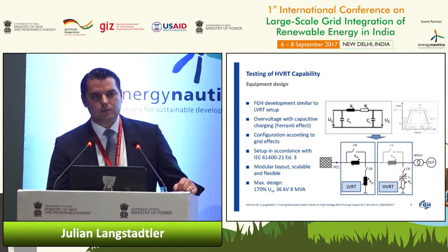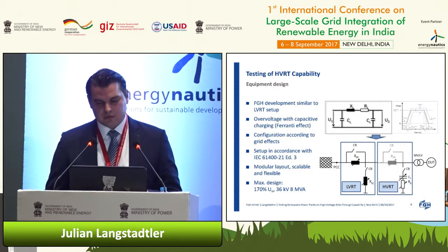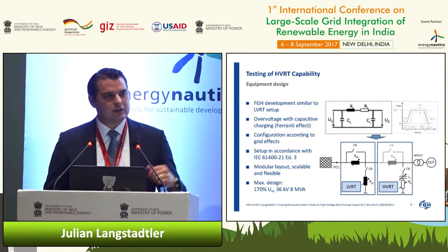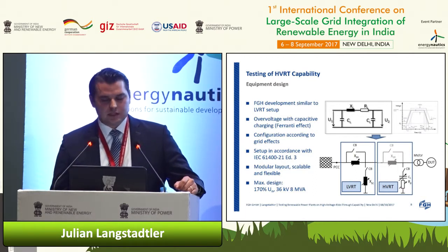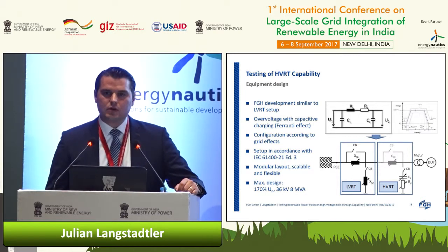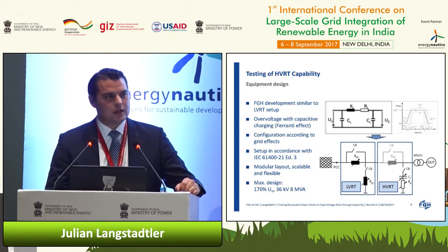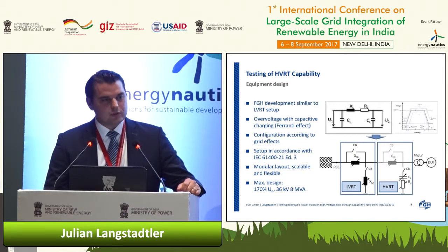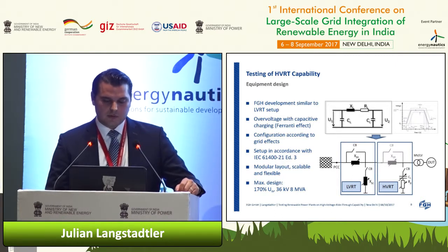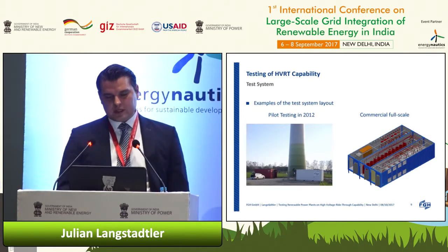That means, on the one hand, you have the possibility to manufacture HVRT standalone test systems, but you can also combine them within an LVRT or HVRT test system. So far, our maximum design was 170% of nominal voltage for overvoltages, rated at 36 kilovolts and up to rated powers of 8 megawatts. Here you can see some examples of such testing systems.